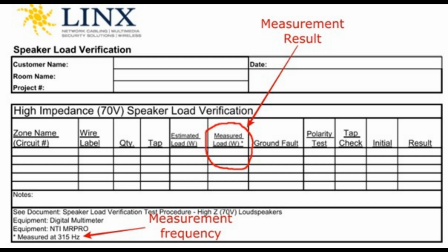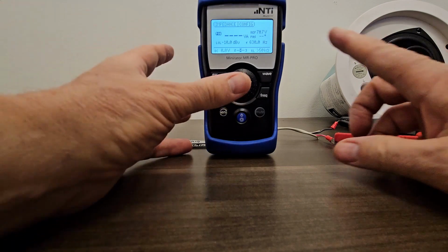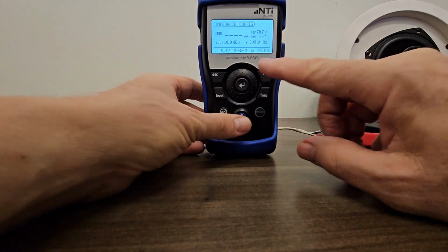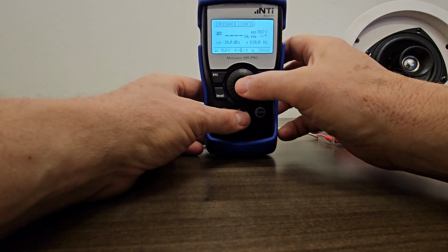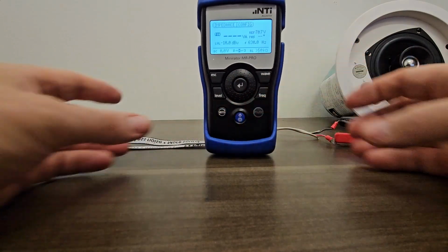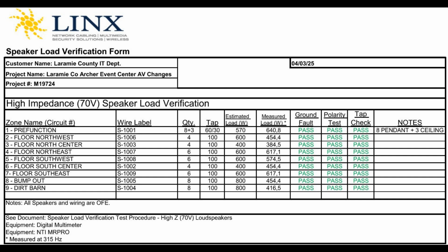You can document the power values by writing this down on the test document or taking a screenshot of the test generator. To take the screenshot, press the on-off button and enter button simultaneously to store the screenshot in a folder called Screen. The test document should be prepared by the project engineer or field engineer before you begin. This document can be useful for showing user-friendly zone names, speaker wire labels, and expected load, which can help flag potential installation issues.